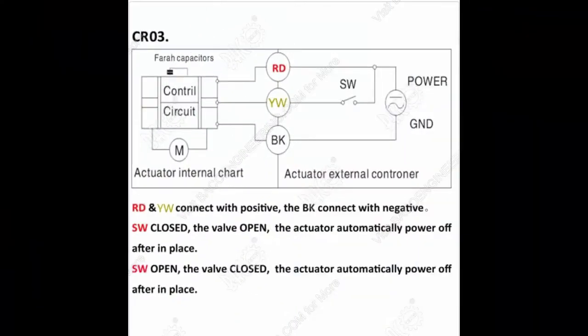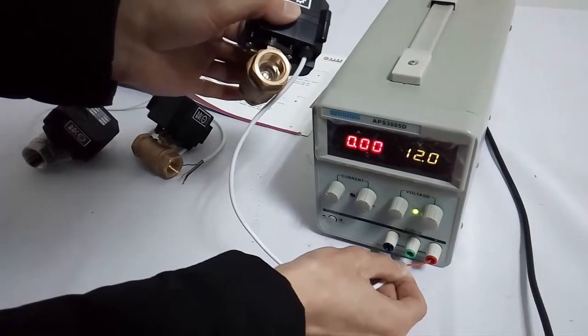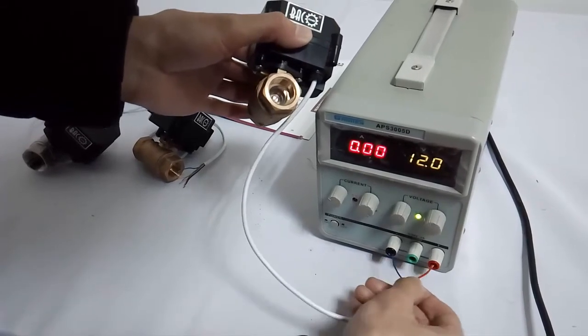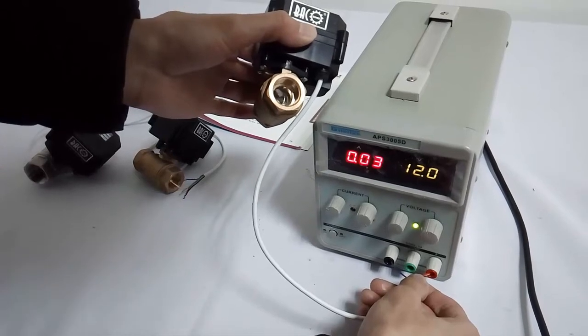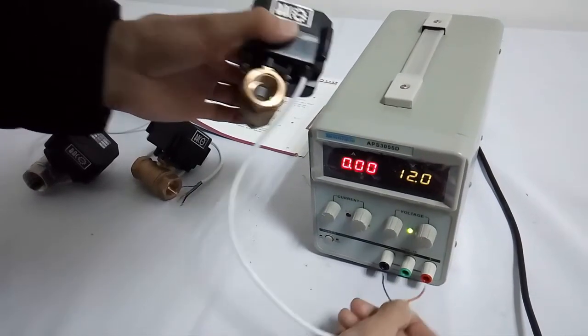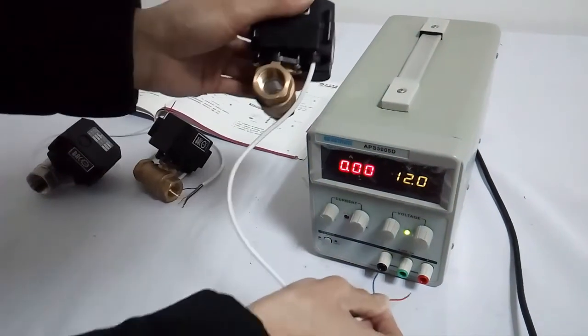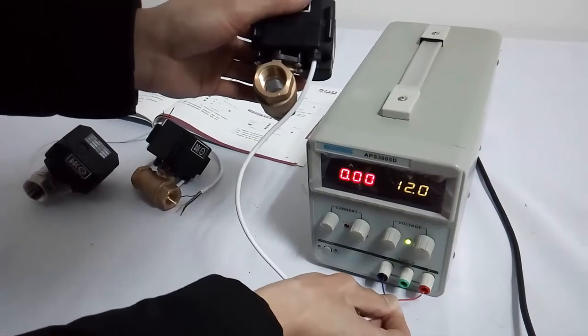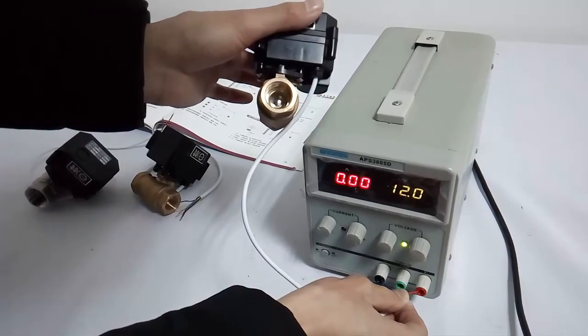Wiring diagram CR03: It has 3 wires — red, yellow, and black. The black must always be connected to the negative pole. When red and yellow are both connected to the positive pole, the valve will be opened. Power off automatically after in place. When red is connected to the positive pole alone, the valve will be closed. Power off automatically after in place.